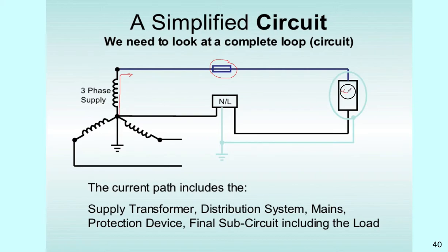We have a load. And protecting that load is a protective Earth. So, encircling the load. So, if something was to fail between the active and the device. It's designed so it will fail to the protective Earth. The whole idea means that at this point here. Something called the touch potential. Touch potential never gets above 50 volts.